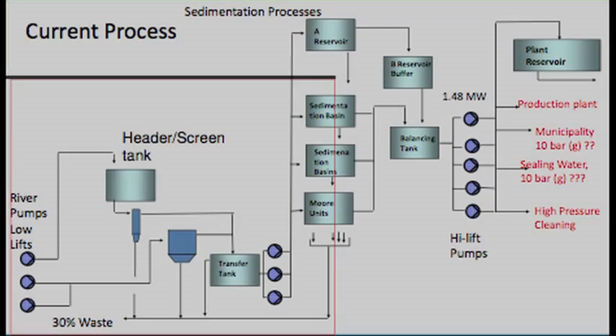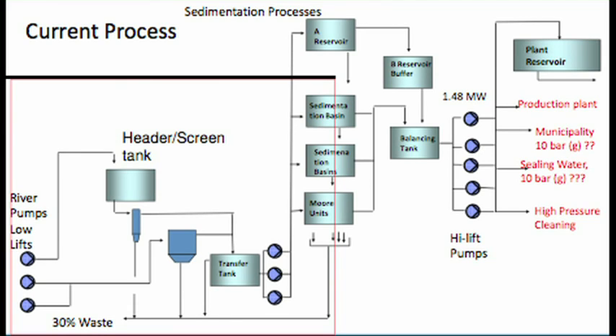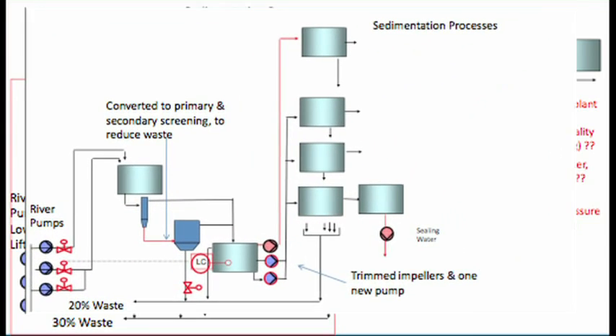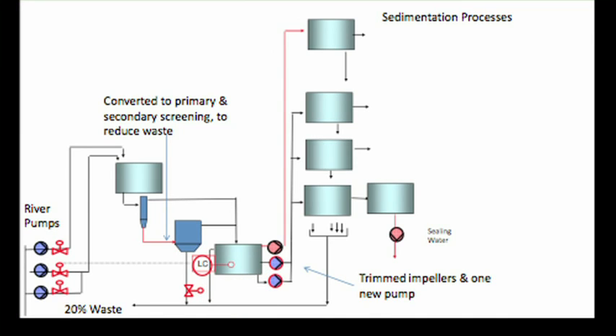What did we do on this section down here? We put in one new pump to supply that 15 meter back pressure or static head. We downgraded these two pumps, trimmed the impellers, and added one new pump. As you probably have noticed by now, we didn't put any variable speed drives onto this in this project, and it's, I guess, a bit what Gunnar was talking about. Generally, the major component of all your system curves is static head in this application, because you're pumping to a high head here, and up to the mill.